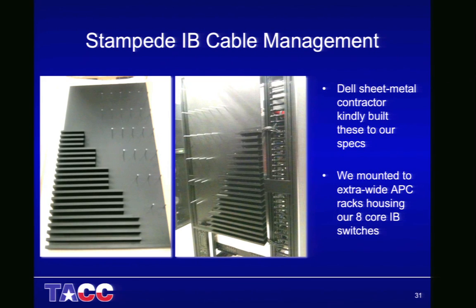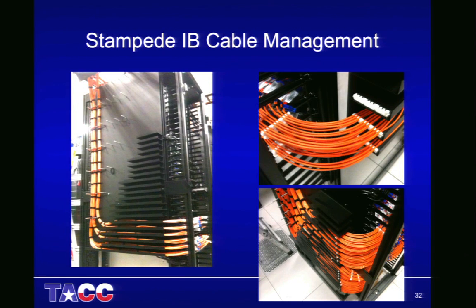Then we mounted it on the side of our compute racks. You'll notice that we take the sides of our panels off to accommodate this, but overall it looks pretty clean. We do tend to use extra wide racks, so that when we mount these on the side, we still have a little bit of space to stand and do the cabling after it's all said and done, because we still adhere to a typical floor layout where we have one compute rack on a floor tile. This is what it looks like when it's all done.